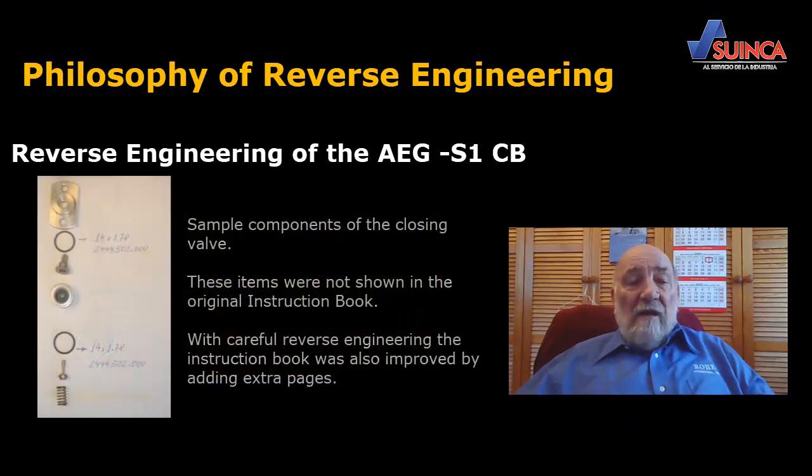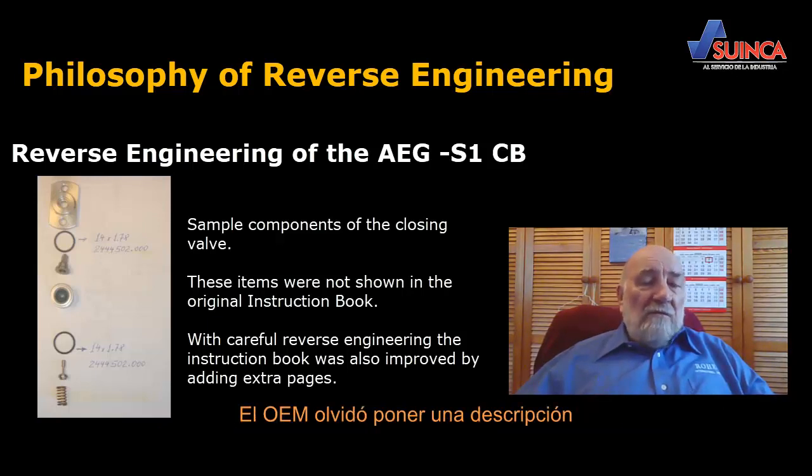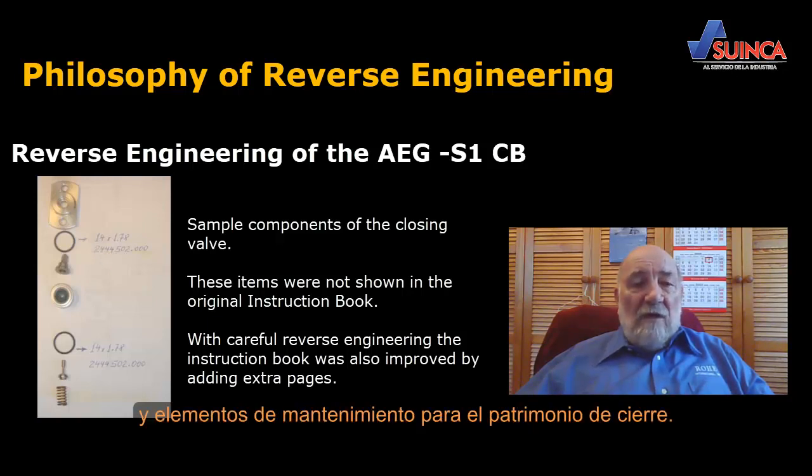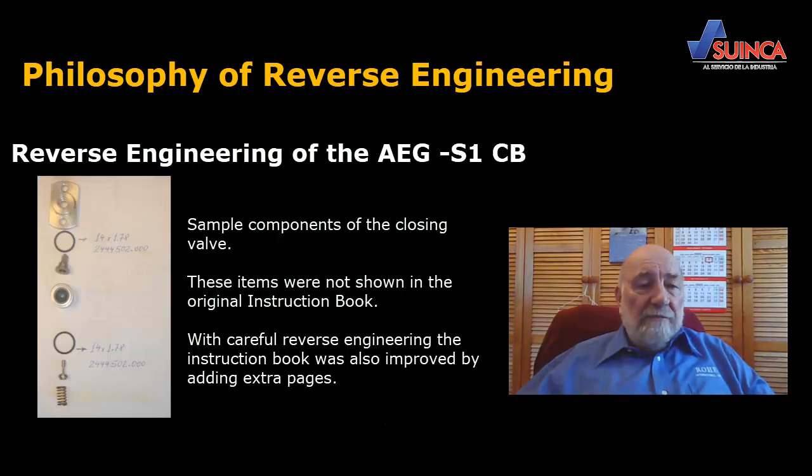On the closing valve, we found this section was not even in the original manual. The OEM forgot to put a description and maintenance items for the closing valve. So we created a new page in the book and added the gaskets and seals needed for the closing valve.